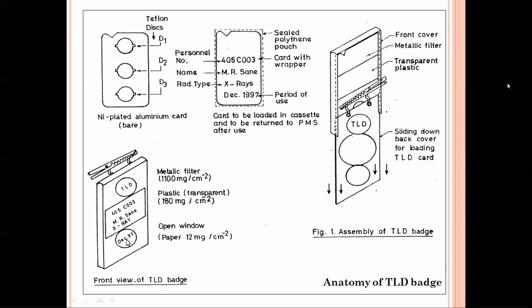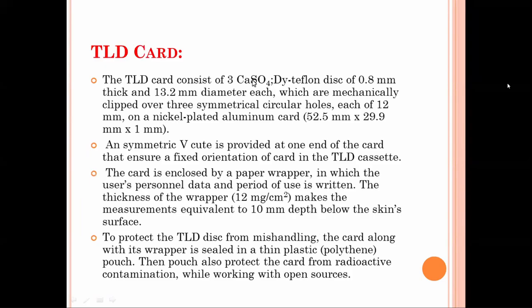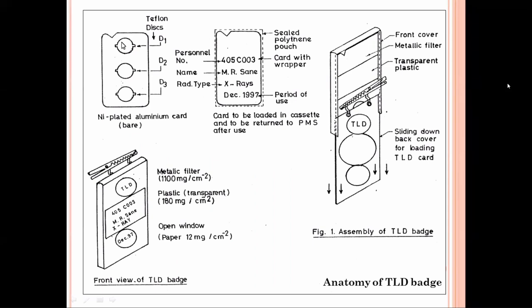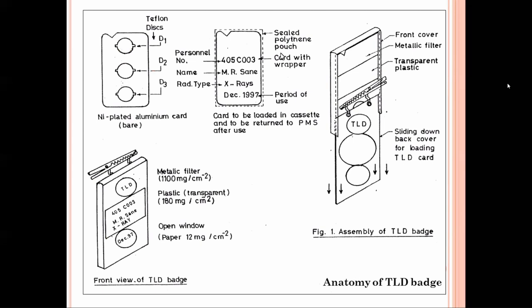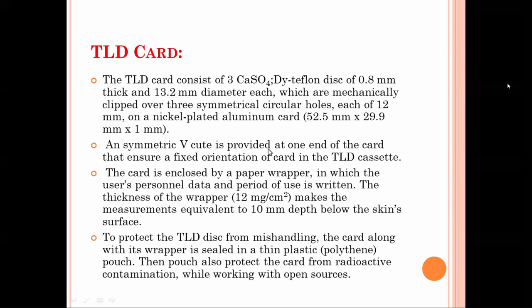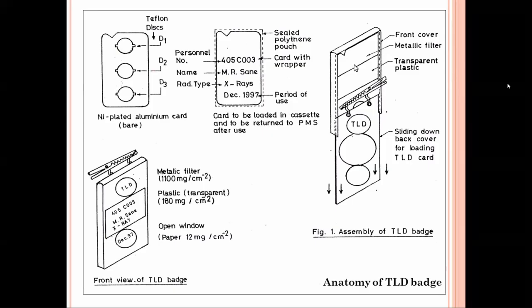The TLD disc is 0.8 mm in thickness and 13.2 mm in diameter, mechanically clipped over three symmetric holes of 12 mm diameter. The card dimensions are 52 mm in length, 29.9 mm in width, and approximately 1 mm in thickness. A symmetric V-cut is provided at one end of the TLD to ensure correct orientation of the card, so it cannot be incorrectly oriented when placed in the cassette.